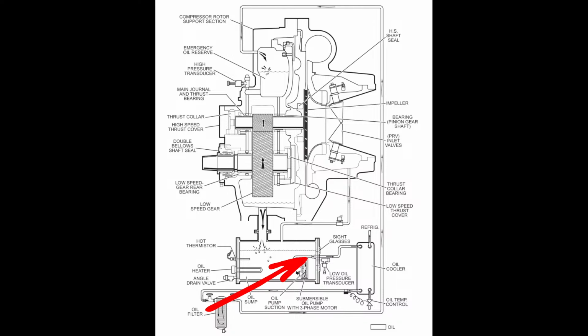The only ones that'll come out are if it's got the plastic flex whip on where the sensor threads into the well itself. If you see that, like you see on Trane water temp sensors, that's an immediate indication that you can change it. Well, actually, the water temp sensors on the Yorks have those same plastic flex whips to help take some of the strain out of the wire flexing. So that's a dry well. Just as a reminder.